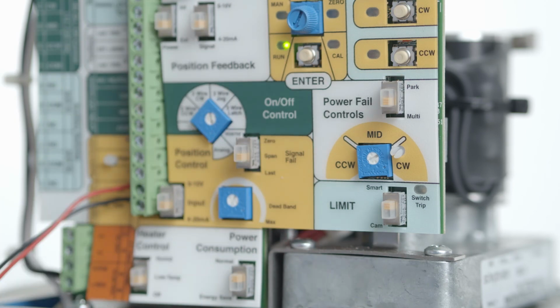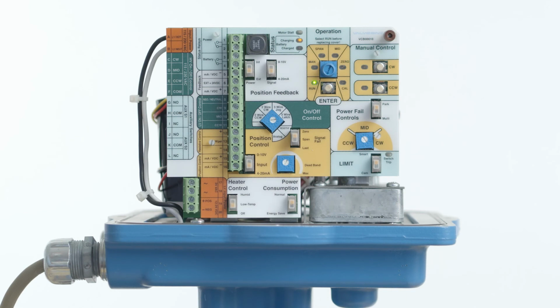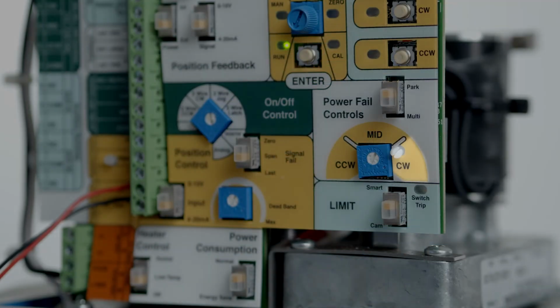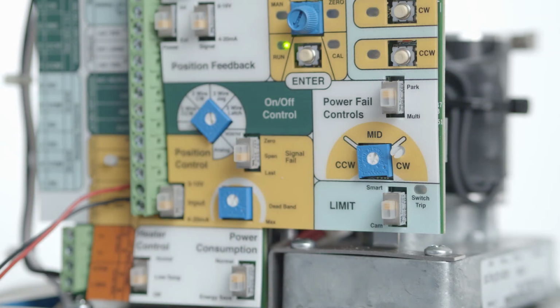If multi-mode is selected, the unit will continue to respond to a control signal until either the signal is lost or the battery level reaches a low-level threshold. In either case, the battery will drive the actuator to the park position. Finally, we need to select the fail position. The actuator can drive to the full clockwise position, to a mid position, or the full counterclockwise position. To change this setting, use a small flat blade screwdriver to turn the power fail control selector.